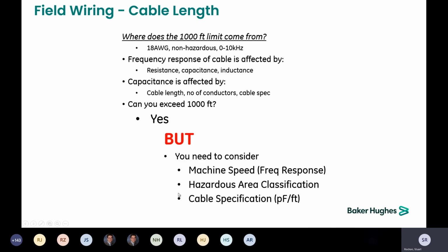Using things like barriers can actually increase the available usable cable length, and going to a better capacitance cable can also extend that range. So we've got a calculator. If you need to go greater than 1,000 feet from the Proximitor to the monitoring system, get in touch with us and we can help you sort out what kind of cable you need to source to do that.